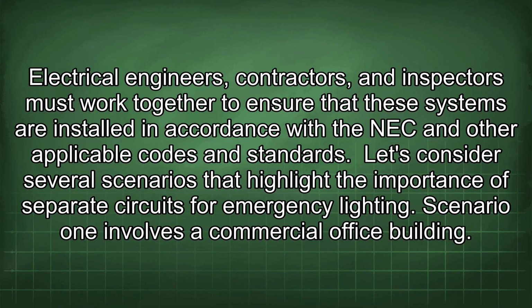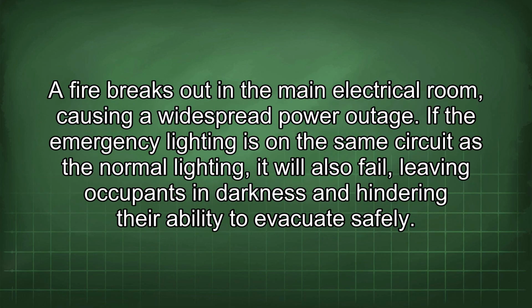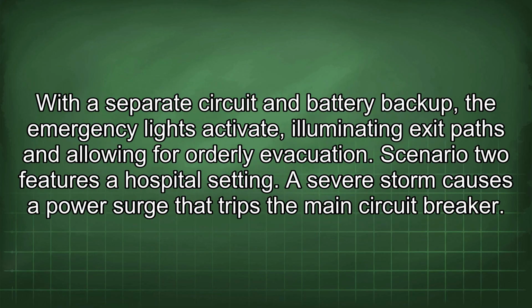Let's consider several scenarios that highlight the importance of separate circuits for emergency lighting. Scenario 1 involves a commercial office building. A fire breaks out in the main electrical room, causing a widespread power outage. If the emergency lighting is on the same circuit as the normal lighting, it will also fail, leaving occupants in darkness and hindering their ability to evacuate safely. With a separate circuit and battery backup, the emergency lights activate, illuminating exit paths and allowing for orderly evacuation.